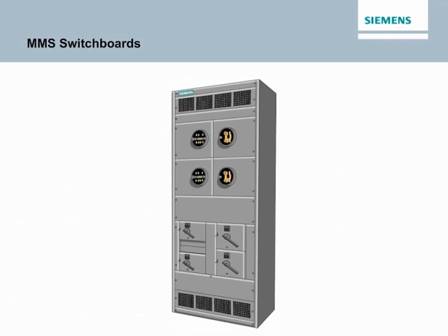Siemens MMS switchboards provide a high quality multi-metering solution for areas where EUSERC compliance is not necessary. The switchboard main service is rated up to 4,000 amps for the following services: 208/120, 3 phase, 4 wire and 480/277, 3 phase, 4 wire.